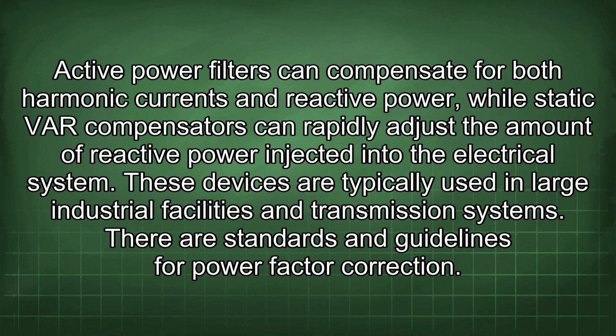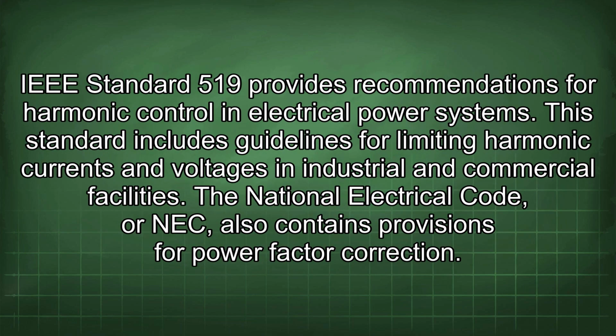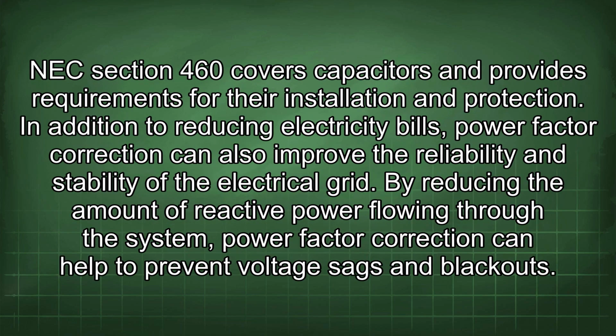There are standards and guidelines for power factor correction. IEEE Standard 519 provides recommendations for harmonic control in electrical power systems. This standard includes guidelines for limiting harmonic currents and voltages in industrial and commercial facilities. The National Electrical Code, or NEC, also contains provisions for power factor correction. NEC Section 460 covers capacitors and provides requirements for their installation and protection.